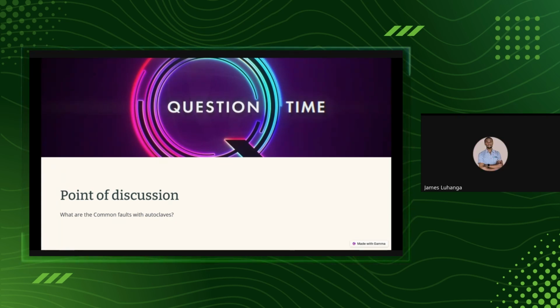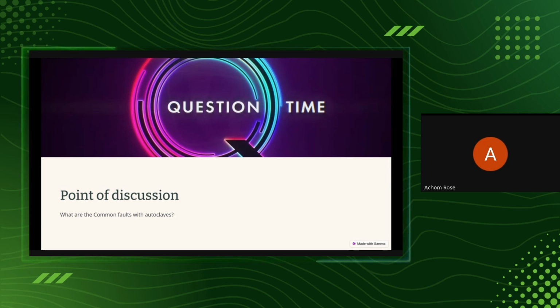Yeah, so for calibration, like I was mentioning, the 17025 standard does not allow us to give recommendations for the next due date to the client. So most of the time we leave it to the users to determine the next calibration date of an equipment, even for autoclaves. But most of the time, the manufacturers say at least once a year. So it is upon you to see whether your clients perform calibrations at least once a year, or whether they perform a verification and realize that the equipment can stay for 3 years before recalibration, which is also fine, because this recalibration has so many factors.